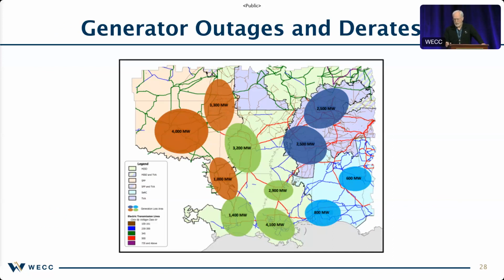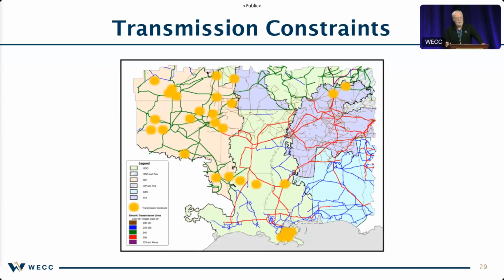You can see several thousand megawatts of generation lost due to this event throughout the territory that was affected. One of the other things they identified during the operation of the power system: as the generation that's serving load is lost, then you have to get power from somewhere else. And if that power comes from a generator that's remote, or it comes from another balancing authority beside you, then it has to travel across the power system.